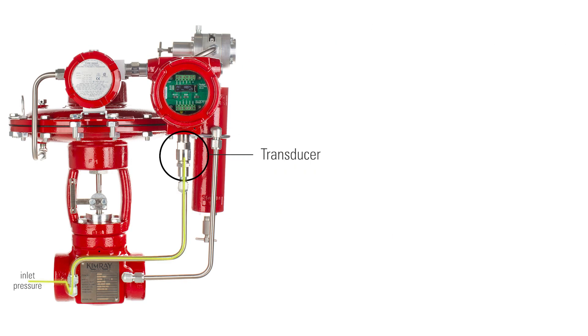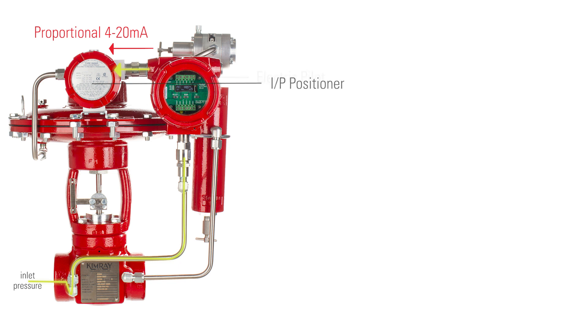The transducer measures process pressure and gives a raw 4 to 20 milliamp signal to the pilot. The electric pilot takes that signal and converts it to a proportional 4 to 20 milliamp signal and sends that to the I/P positioner.